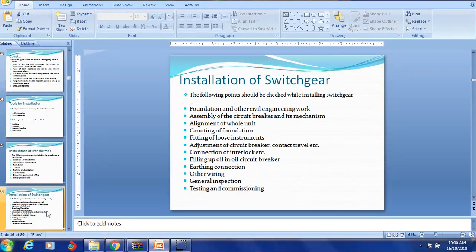Installation of switchgear: we need to consider foundation and other civil engineering work, assembly of the circuit breaker and its mechanism, alignment of the whole unit, grouting of foundation, fitting of loose instruments, adjustment of circuit interrupting devices, connection of interlocks, filling up oil in oil circuit breakers, earthing connection and various other things.